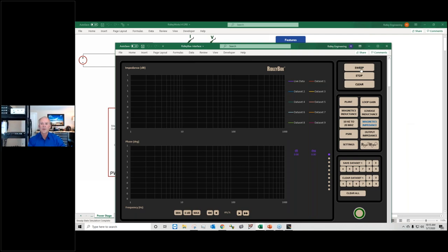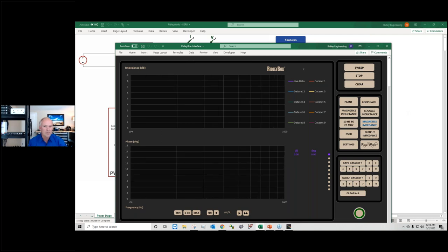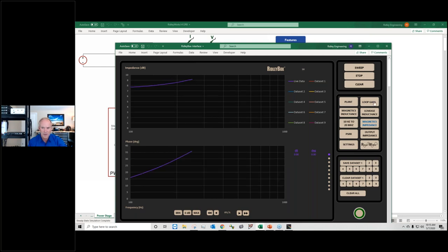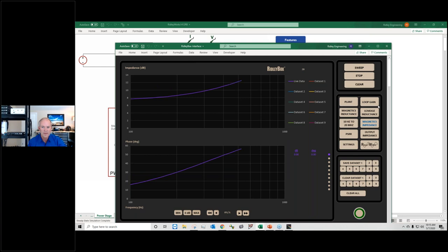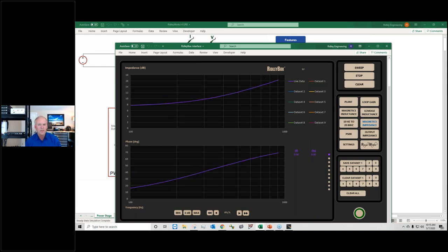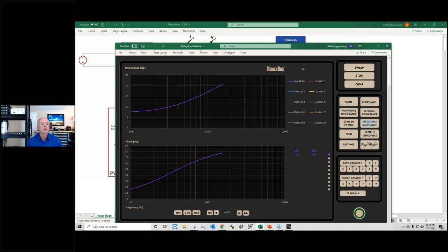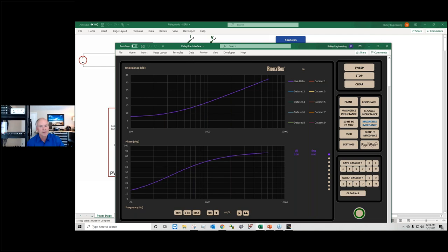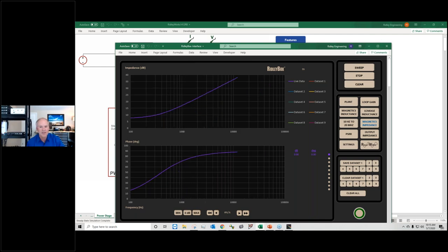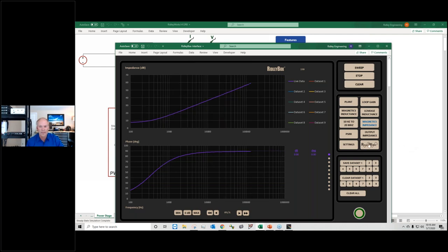Now we're going to sweep. Sweep initiated, we're going to sweep the impedance of the primary of the transformer. This is our control panel for our frequency response analyzer, probably the first one that talks to you. We find people have these analyzers in their lab and don't remember how to use them, so ours talks to you and shows little pictures of how it's set up. Now we're sweeping here, this is our impedance of the transformer. It's great sweeping impedances, but if you don't have a comparison to what it's supposed to do, it's kind of hard to read.